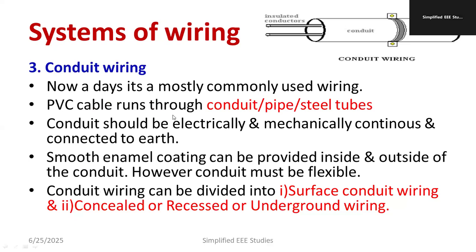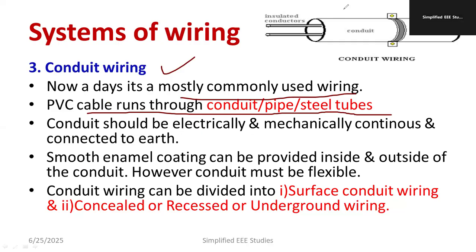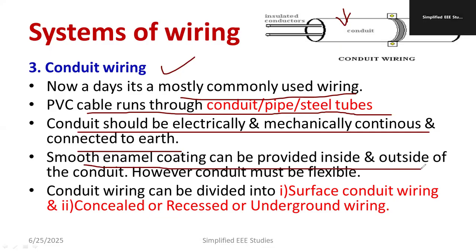Next is conduit wiring, which is the most commonly used wiring today. The PVC cable runs through a conduit — a pipe or steel tube. The conduit provides mechanical strength. The conduit should be electrically and mechanically continuous to earth. A smooth enamel coating should be provided on the conduit, and the conduit must be flexible to avoid brittleness or breakage.